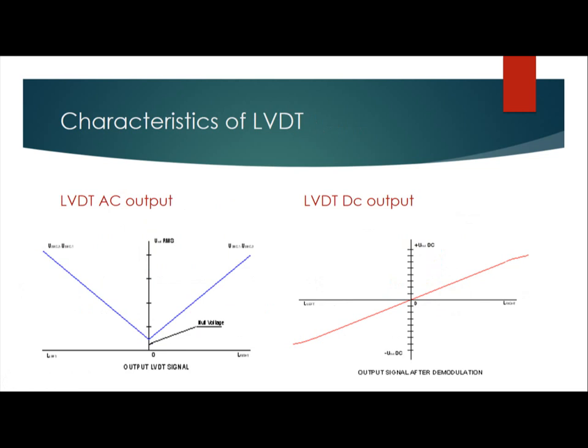There are two types of output in LVDT. As discussed previously, if the moving core is centered between the two secondary coils, there is a null voltage output of zero. If it is moved towards S1, the resulting voltage will be E1 minus E2, and in the other direction it will be E2 minus E1.